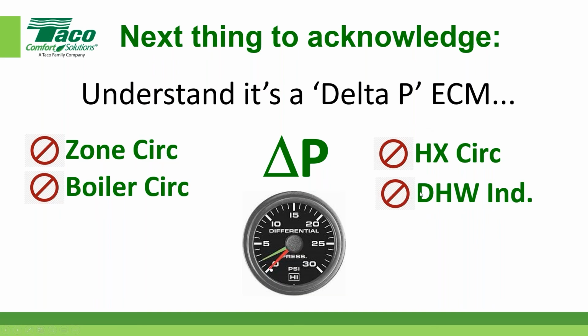And domestic hot water indirects, they're just another form of heat exchanger. We typically want to satisfy those as fast as possible. We want to get as much flow through that coil as quickly as possible. And if you think about the piping scheme of those, there's nothing in there to give the circulator any feedback to make a decision. So again, take the ECM and put it in a fixed speed or an appropriate mode that makes sense for the job at hand.